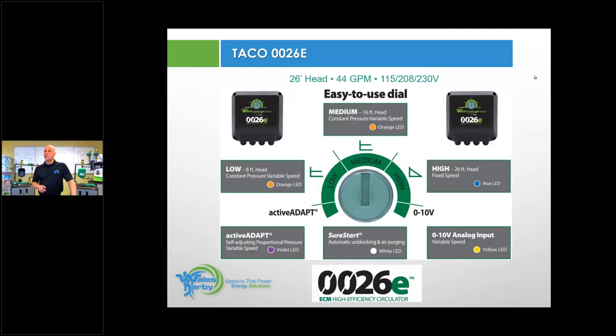And just to give you an idea here, a blown up picture of the 0026E. So low tells you it's 8 feet. We have active adapt, which will work with, if you have Danfoss valves or something like that on a system, it will actively adapt to the system. If you do a big zone valve job, as you close zone valves, it will actively adapt and reduce the flow of the system when you start to close zone valves down. The 0026E and the 0034E are both 115, 208, 230 volt out of the box. So you're not buying different circulators for different voltages.